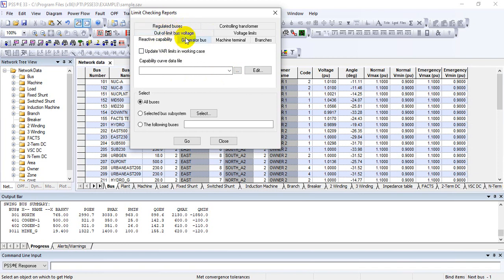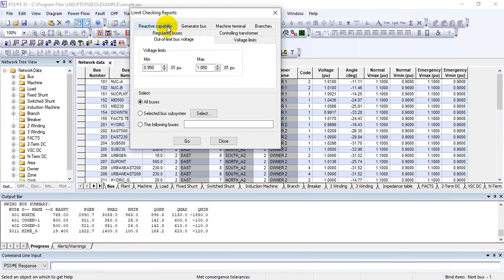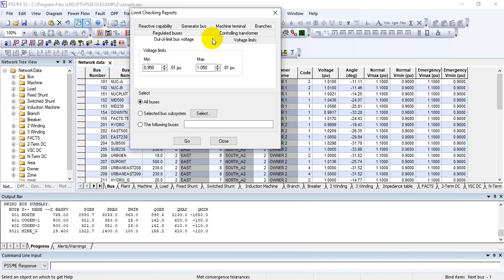The next important point is out-of-limit bus voltages. The voltage limits, as per grid code planning criteria, are plus or minus five percent — this is the threshold. Based on that, if any buses are violating these limits you can generate this report. Similarly, you can generate a branch report as well. As per planning criteria, all branch thermal ratings must be within 100 percent of the loading, so any transmission line or two-winding transformer violating that limit can be seen here.